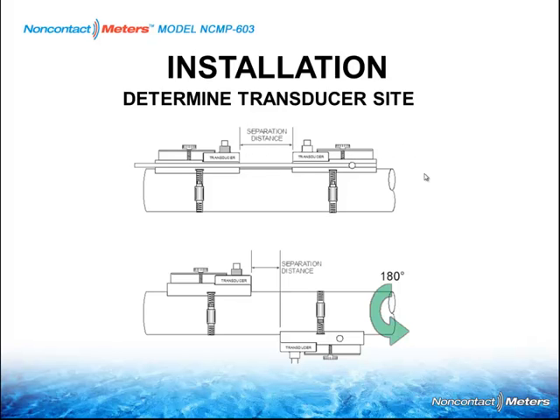Now note, this is pictured for your view at 12 o'clock, but as we move forward here, we want to keep the device off of 12 and 6 o'clock just in case you got air and in case you got bubbles here. So on the larger pipe applications, we have to go to a Z configuration. Again, one would be at 9 o'clock and one would be at 3 o'clock. Again, the transducer cables are on the inside of this distance here. And when you go to the single path, single crossing, or Z configuration, the distance will be about half between the two transducers because you only have one path going across, 180 degrees across from each other. Not as easy as this here.